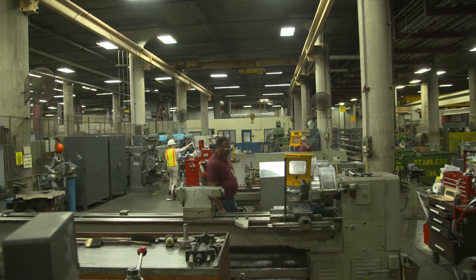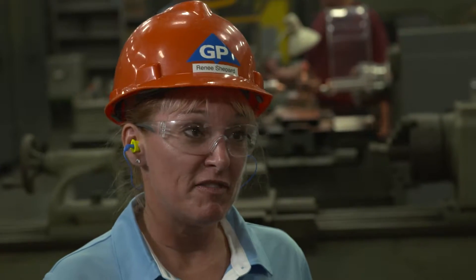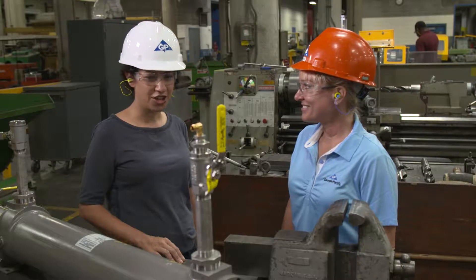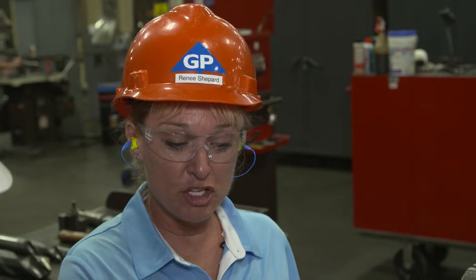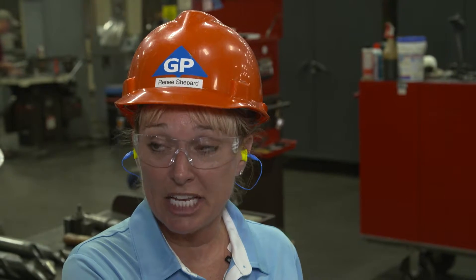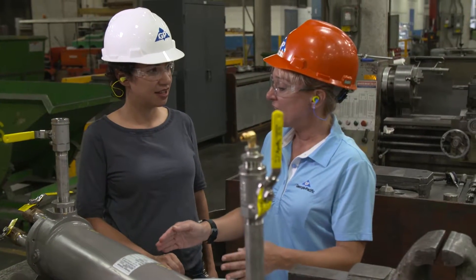We're in Savannah River Mill's machine shop. Based on the field investigation, we figured out it was the heat exchanger that was having an issue causing the temperature problem. We brought it down here so we could do further investigation — take it apart and take a look. This brings us to engineering step number two: design. As engineers, we have to go back and look at the design and intended function of the equipment. In a heat exchanger, cooler fluid flows through the tubes and hotter fluid flows through the shell. In our case, the temperature going through the tubes was getting too hot. The overall condition of the unit appears fine, so we need to dig deeper to make sure it's functioning as designed.